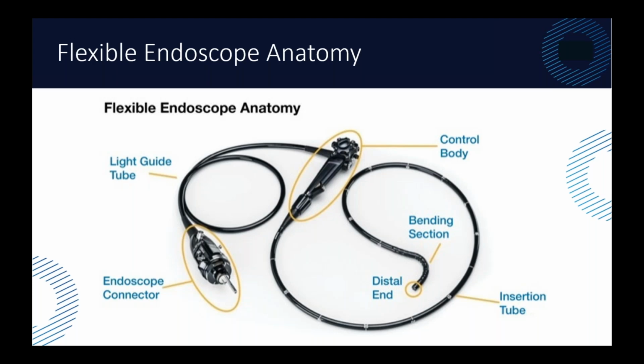Right after the tip is this bending section, this bending rubber. It's a very flexible section that the doctors can twist and turn to get better images and to see things. And this is true for ultrasound and endoscopy. Because that rubber has to be flexible, this is a point of weakness for both types of transducer. Most of the problems that we see with water intrusion, if they aren't caused in central sterile by putting the whole probe in water in certain situations where you shouldn't, the problem comes from here. Then after that, the bending rubber areas are probably about that long.